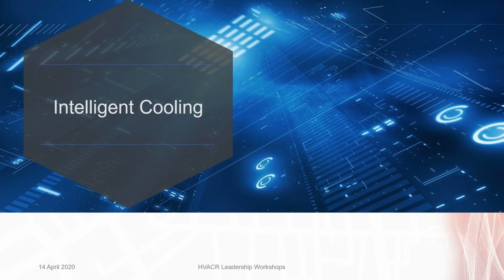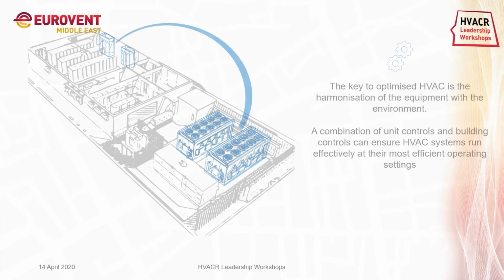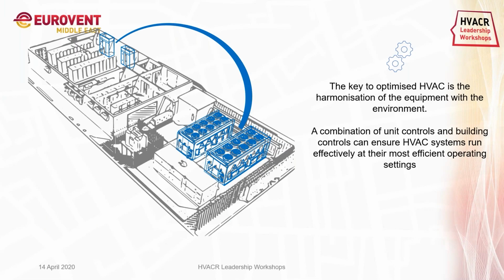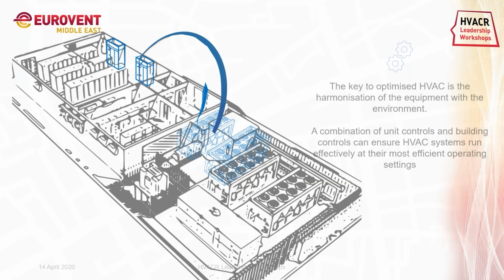Now coming to the intelligent cooling. Of course, the key to achieving energy saving and impressive PUE, or power usage effectiveness, metrics is through the use of intelligent control systems. The CRAC units are equipped with intelligent controls. So whenever the equipment controls and the environment are harmonized, we can optimize and have a higher efficiency system. So the combination of unit controls with the building controls or a BMS system can ensure HVAC systems run effectively at the most efficient operating settings.